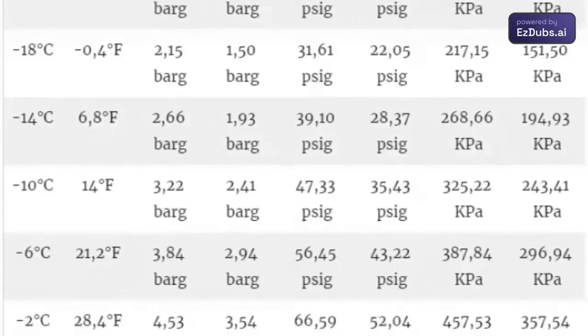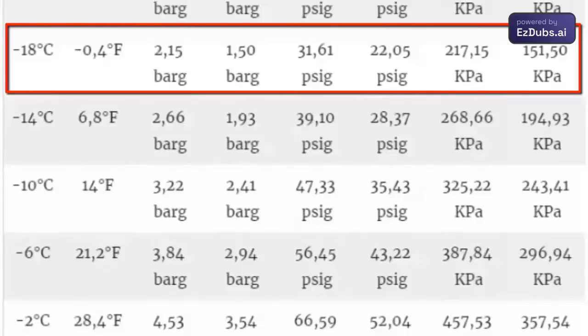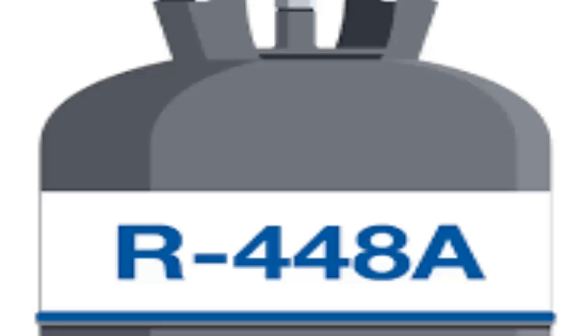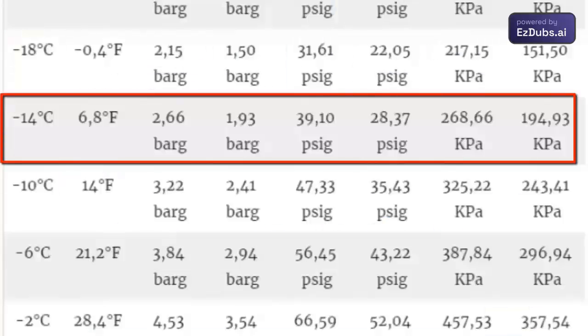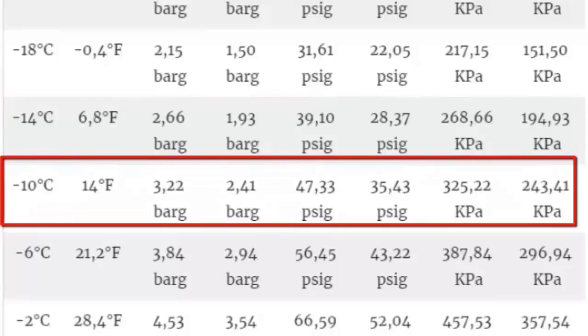1. To achieve a temperature of minus 18°C (minus 0.4°F) in the evaporator, a gauge pressure of 1.50 bar, equivalent to 22.05 psig or 151.50 kPa is needed. 2. To achieve minus 14°C (6.8°F), a low gauge pressure of 1.93 bar, equivalent to 28.37 psi or 194.93 kPa is required. 3. To achieve minus 10°C (14°F), a low gauge pressure of 2.41 bar, equivalent to 35.43 psi or 243.41 kPa is needed.